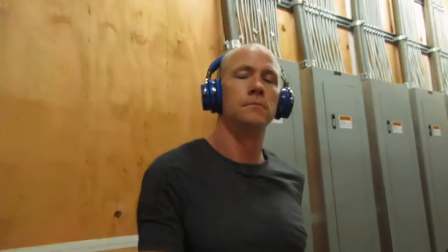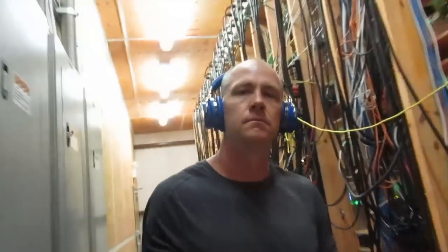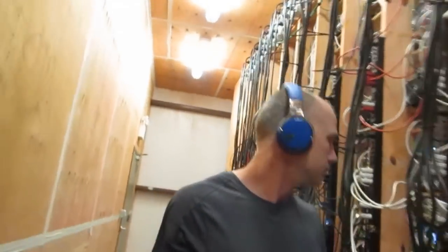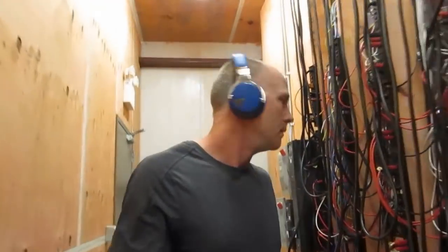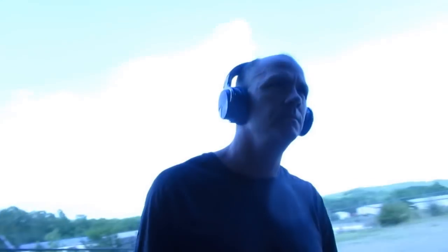Good build out here. Now let's walk to finish the tour. I'll take you down this cold aisle and out one of these other doors so you can see what things look like on the outside. Now again, this is all fireproof wood. We've got motor controllers for the fan motors, and these are set up so that if power goes off and comes back on, that the fans will come back on as well. That's an important tip there.